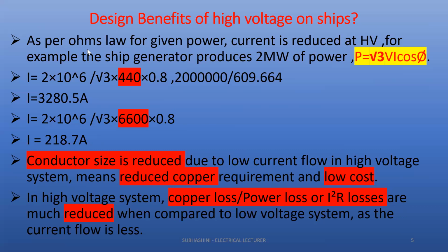For example, I'm taking a ship generator that produces 2 megawatts of power. This power is equal to root 3 V I cos phi. This is our formula for power. From this I'm going to find the full load current I. So I is equal to power divided by root 3 V cos phi, that is 2 into 10 to the power of 6 divided by root 3, using a voltage of 440 volt, and cos phi of 0.8, since I'm using inductive loads, motors. The full load current value I get is 3280.5 amperes, so approximately 3300 amperes.